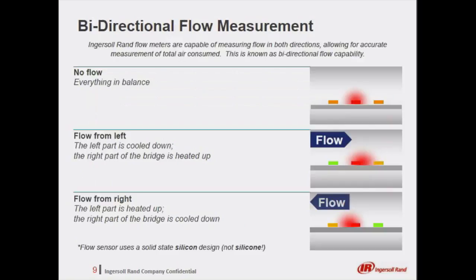All of Ingersoll-Rand flow meters come standard with bidirectional flow measurement capability. This allows for accurate measurement of the total air consumed, and by using a heater on a Wheatstone bridge, the flow meters are able to determine flow by the air passing over the sensor system. As the air on one side of the sensor system cools down, the direction is determined. The degree at which the temperature drops determines the amount of flow. The sensor uses a solid-state silicon design, and it's important to point out that while this is different from silicone, we definitely want to avoid that silicone.